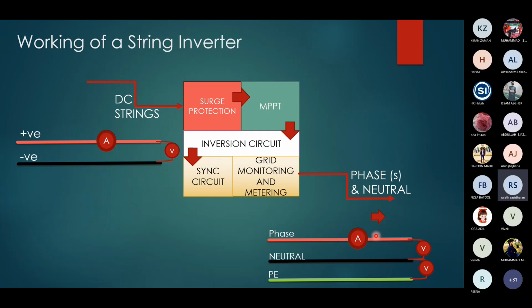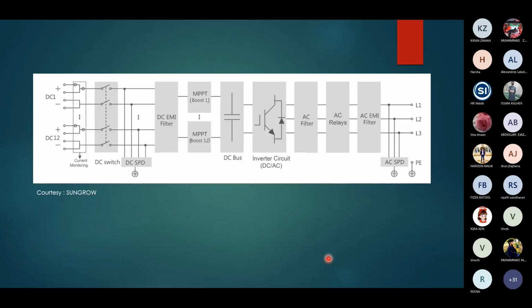Monitoring and metering is nothing but you need to know the voltage between the poles. You need to know the respective voltage between a certain phase and the neutral. And also you should know if there is any leak current happening or severe circuit issues, so you have to monitor between the neutral and the ground also. In some commercial applications, in larger scale plants especially, this neutral is missing. It is not required, so we keep the plant in a floating status.